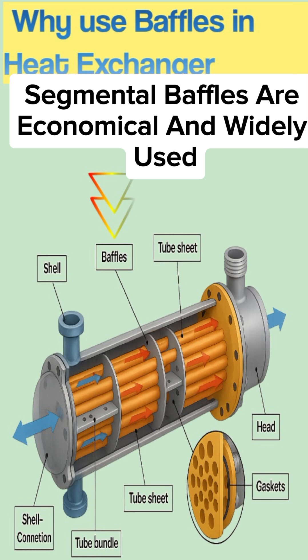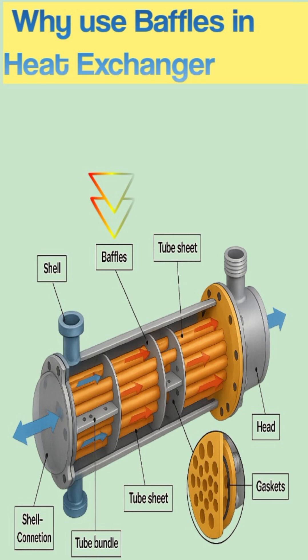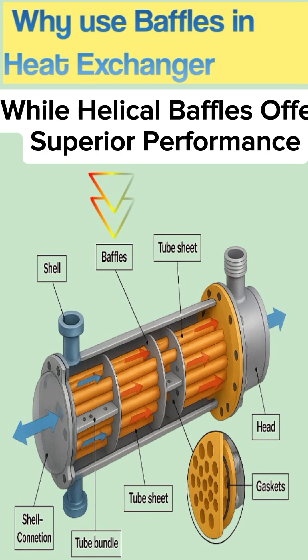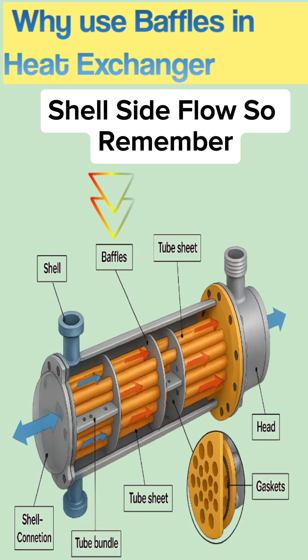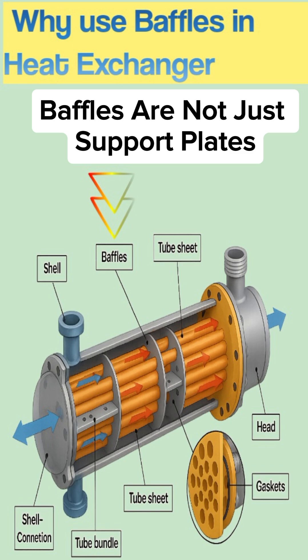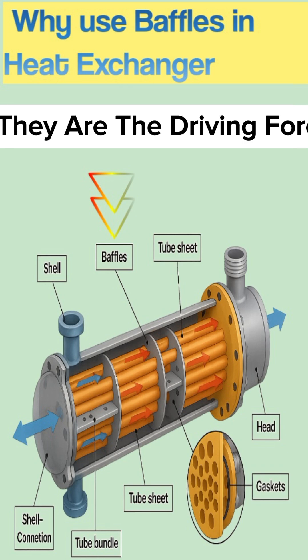Segmental baffles are economical and widely used, while helical baffles offer superior performance with lower pressure drop. Longitudinal baffles are used to create two or four pass shell side flow. So remember, baffles are not just support plates — they are the driving force behind efficient heat transfer.